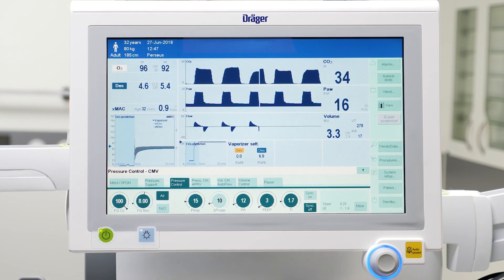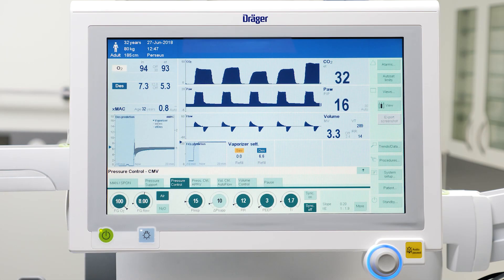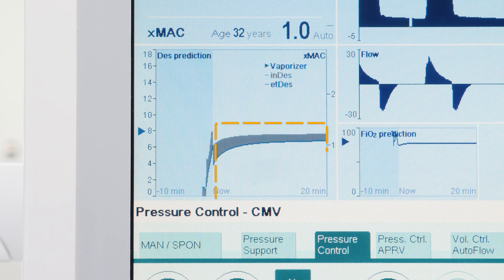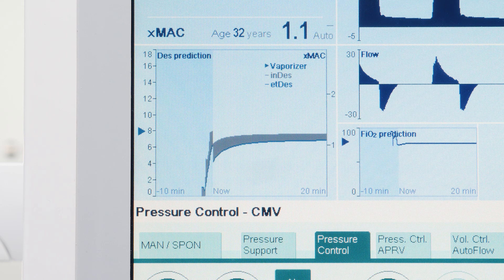Draeger Perseus A500 can offer the intelligent predictive functions VaporView and O2 prediction, when used in conjunction with Vapor 3000 and D-Vapor 3000. The system visualizes both the inspiratory and the expiratory volatile agent concentration and the inspiratory oxygen concentration prediction over the next 20 minutes and a trend of the past 10 minutes. These features offer higher levels of safety and transparency and make the recovery phase easier to manage.